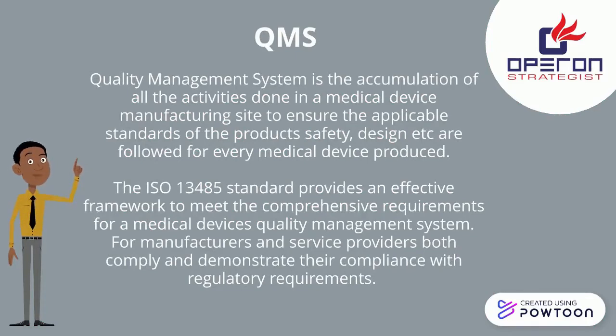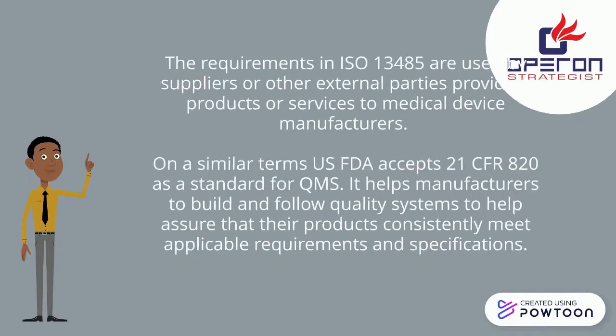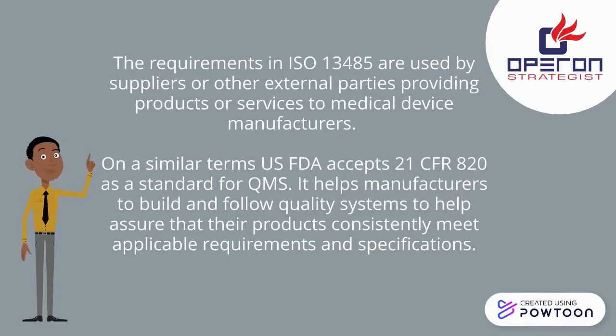QMS. Quality Management System is the accumulation of all the activities done in a medical device manufacturing site to ensure the applicable standards of the product's safety, design etc. are followed for every medical device produced. The ISO 13485 standard provides an effective framework to meet the comprehensive requirements for a medical device's quality management system. For manufacturers and service providers, both comply and demonstrate their compliance with regulatory requirements. The requirements in ISO 13485 are used by suppliers or other external parties providing products or services to medical device manufacturers. On a similar terms, US FDA accepts 21 CFR 820 as a standard for QMS.